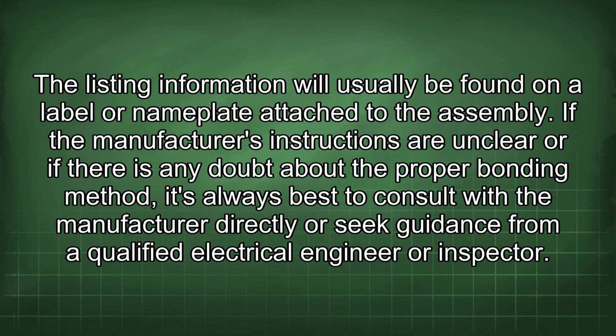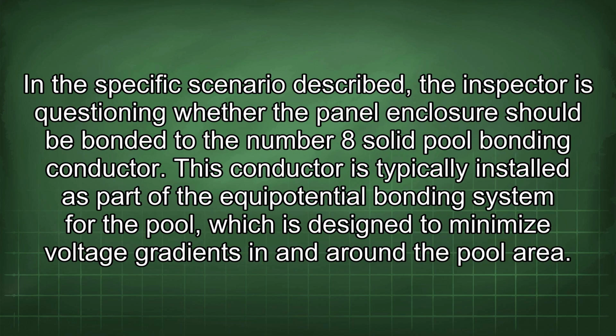If the manufacturer's instructions are unclear or if there is any doubt about the proper bonding method, it's always best to consult with the manufacturer directly or seek guidance from a qualified electrical engineer or inspector. In the specific scenario described, the inspector is questioning whether the panel enclosure should be bonded to the number 8 solid pool bonding conductor. This conductor is typically installed as part of the equipotential bonding system for the pool, which is designed to minimize voltage gradients in and around the pool area.